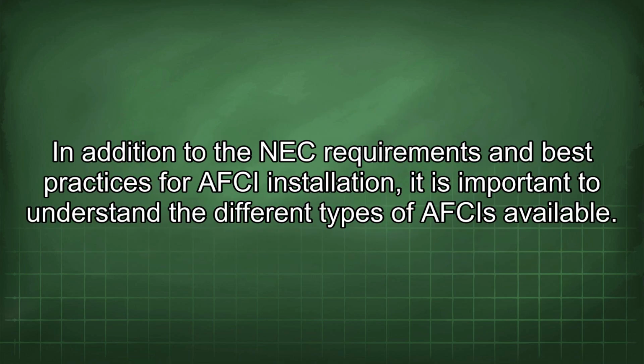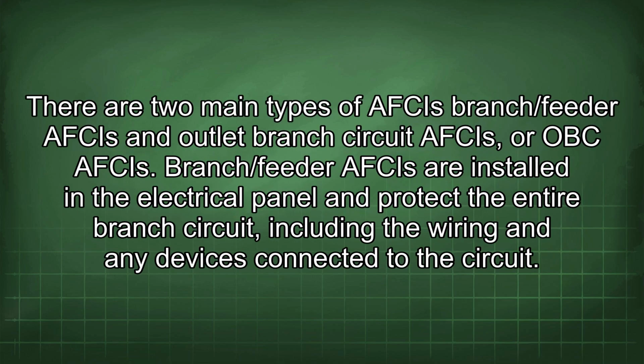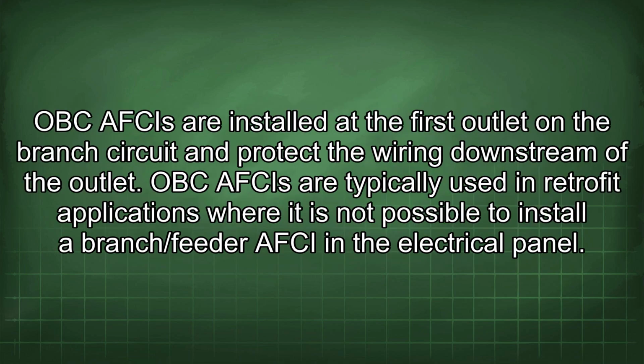In addition to the NEC requirements and best practices for AFCI installation, it is important to understand the different types of AFCIs available. There are two main types of AFCIs: branch/feeder AFCIs and outlet branch circuit AFCIs, or OBC AFCIs. Branch/feeder AFCIs are installed in the electrical panel and protect the entire branch circuit, including the wiring and any devices connected to the circuit. OBC AFCIs are installed at the first outlet on the branch circuit and protect the wiring downstream of the outlet. OBC AFCIs are typically used in retrofit applications where it is not possible to install a branch/feeder AFCI in the electrical panel.